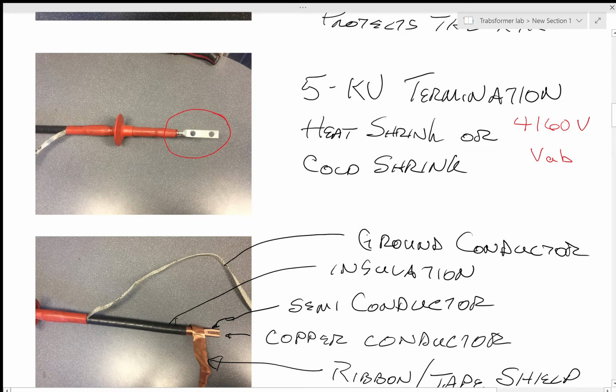Like I say, it's a 5 kV cable. The insulation's thinner, less insulation in there, but it's still got the outer insulation. This has a ground on it right here, a ground tab that makes sure that all those eddy currents and everything goes to ground off the semiconductor. This is called a ribbon or tape shield, completely different from the concentric neutral. You have the semiconductor. That's this black stuff right here around the wire again.